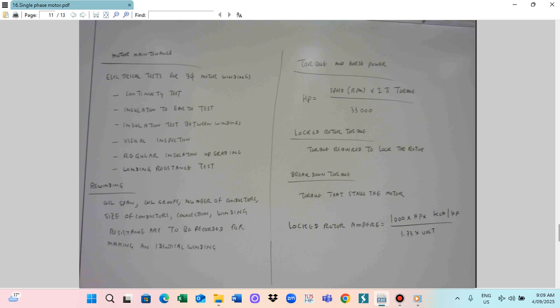Upgrading the insulation means that you take off the motor winding, pull out the insulation, bake the insulation, then put it back and run the motor this way. Otherwise, everything is burned out and you have to rewind. But the thing is that we don't allow the motor to be rewound. So we have to check the motor insulation upgrading. By upgrading the motor, you can avoid the rewinding stage.